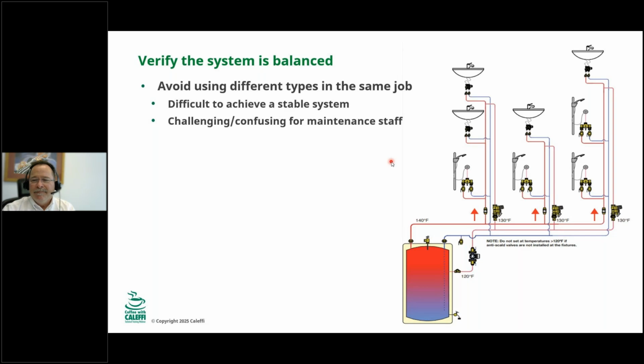We also got a couple additional answers on the run out to fixtures. Art put in some math: if you're talking about half-inch pipe for a 0.35 GPM fixture and you want to get hot water there in under 10 seconds, that math calculates out to 8 feet. We also had an answer from Wisconsin that inspectors are looking for 6 inches, which is a whole different thing. We actually had a Wisconsin-specific Legionella webinar last year, and I'll look for that link while we're still in the call and put it into the chat.